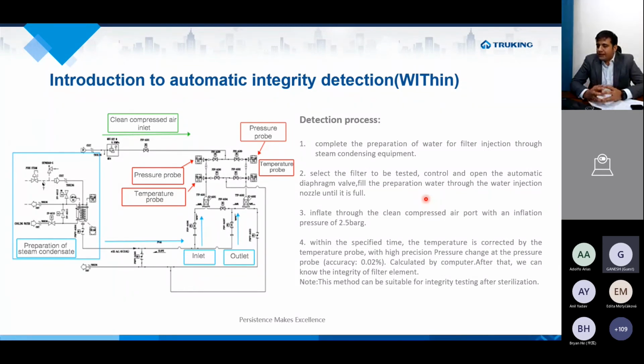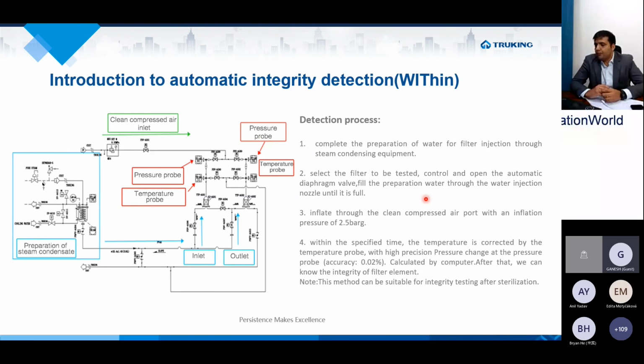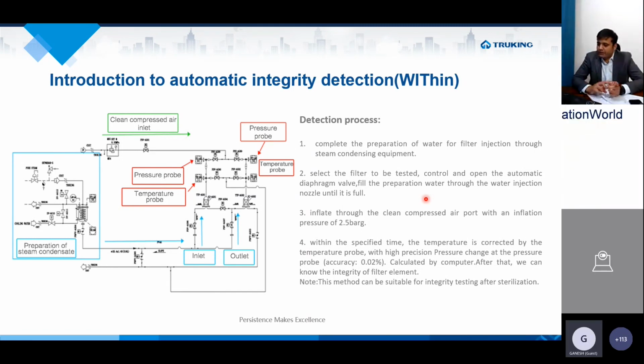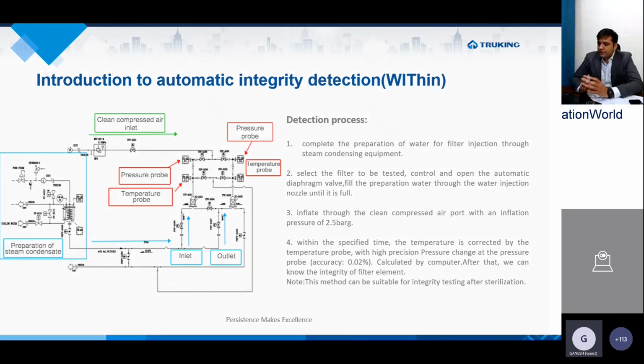The temperature is corrected by the temperature probes with high precision. Pressure change is measured at a pressure probe of 0.02% accuracy, which is calculated by the computer itself, coming from the device. After that, we can know the integrity of the filter element as a final result, which can be used before and after the batch has completed. This method can be suitable for integrity testing after sterilization. So this one is basically done after sterilization, once the filter has been put in place.